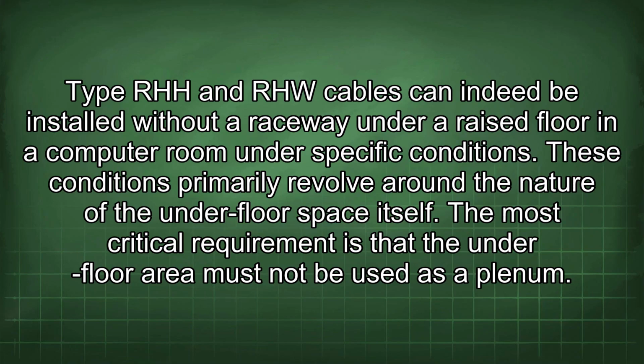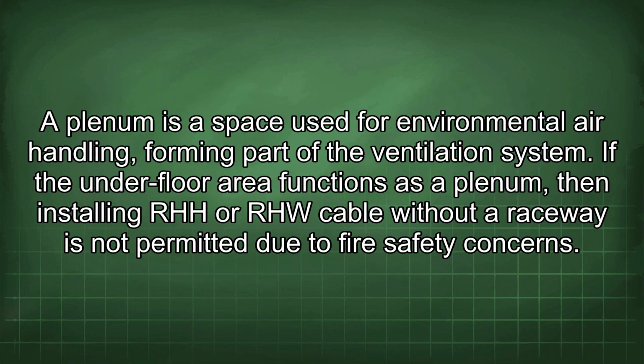Type RHH and RHW cables can indeed be installed without a raceway under a raised floor in a computer room under specific conditions. These conditions primarily revolve around the nature of the underfloor space itself. The most critical requirement is that the underfloor area must not be used as a plenum. A plenum is a space used for environmental air handling, forming part of the ventilation system. If the underfloor area functions as a plenum, then installing RHH or RHW cable without a raceway is not permitted due to fire safety concerns.